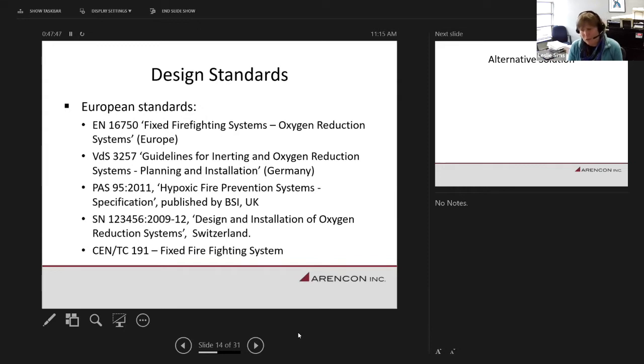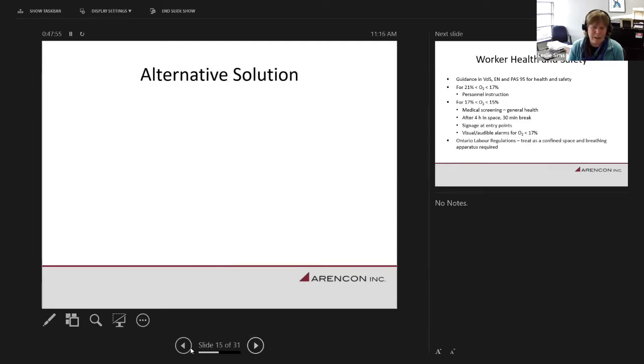And we talk about the objectives, and sorry, this slide is blank and I don't know why. So my apologies, but within the alternative solution, we do have, both in the fire code and the building code, the pathway to allow us to come to alternative designs and alternative systems. So really what we have to do under the alternative solution is to demonstrate that we're going to achieve a similar performance as that we would get from sprinklers. Now, it's not to say it's going to be the same performance because they come at it from two different angles, but the ultimate goal is to limit fire spread and fire growth from the point of origin. So it's not that we're eliminating it.